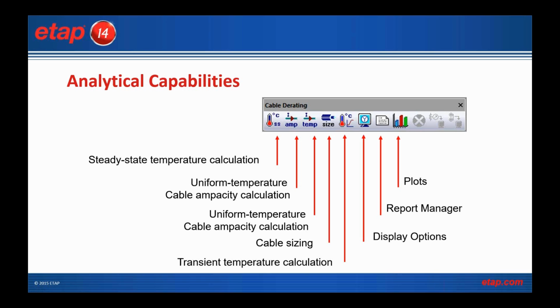And once the current is flowing through the conductor, we assume that current is flowing for an infinite amount of time, and then we calculate a steady state temperature. So this is a temperature over an infinite amount of time the conductor has reached steady state condition, and this essentially gives us the operating temperature of the cable.